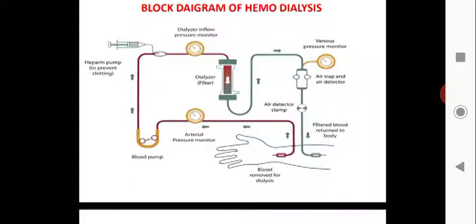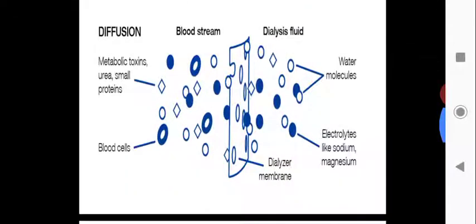Now let's look at the working of a dialyser. The dialyser works on the principle of diffusion. The bloodstream consists of metabolic toxins, urea, small proteins, and blood cells. The blood cells should not diffuse into the dialysis fluid; only waste materials such as water molecules, electrolytes like sodium and magnesium, and urea should diffuse into the dialysis fluid through the dialyser membrane, which purifies the blood by removing waste materials.